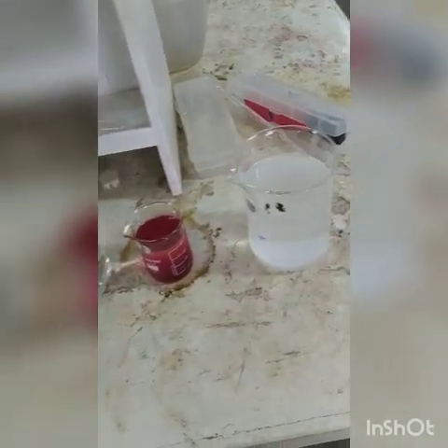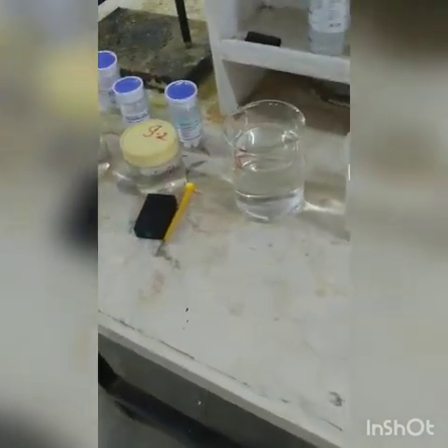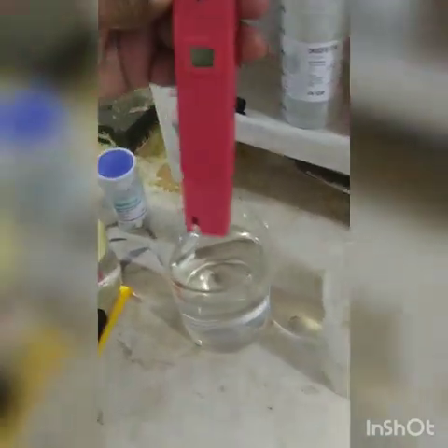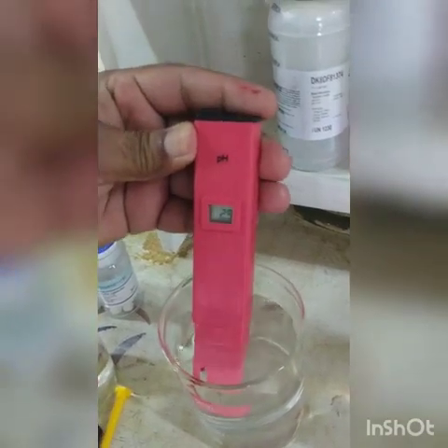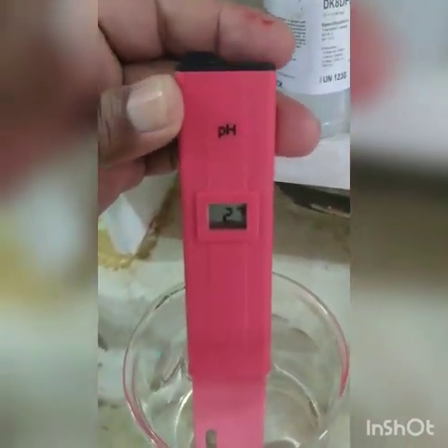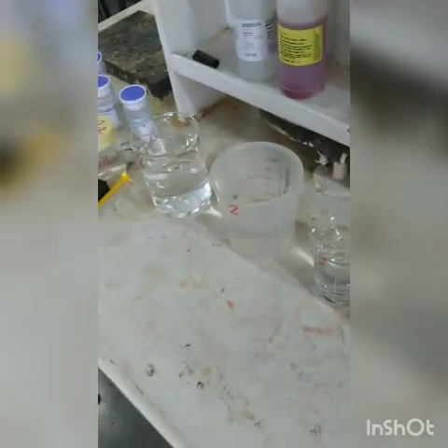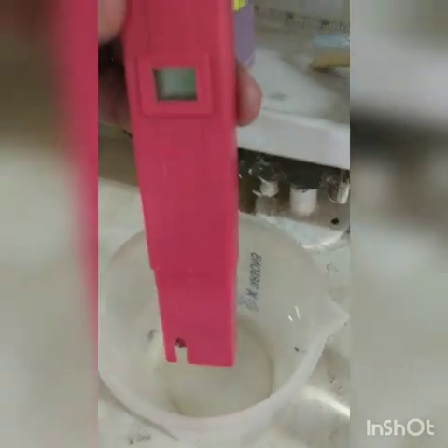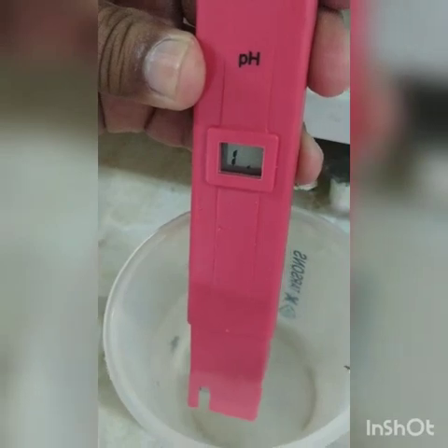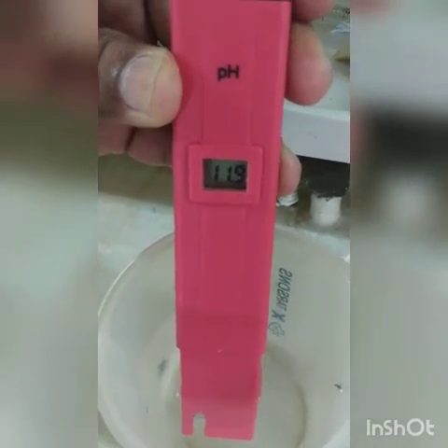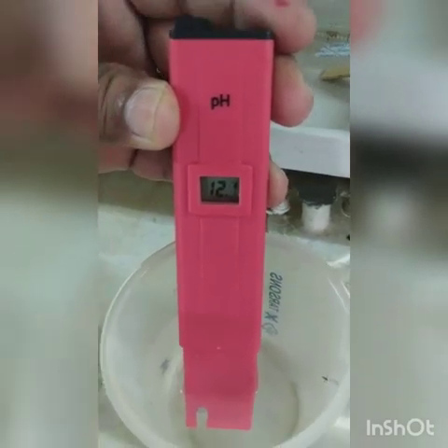So we have 6 different samples that we are going to use for the measurement of pH. So sample 1, you can measure the pH and then we will make the inference. Yes. For sample 1, pH is 2.7. So it is acidic. pH less than 7, the sample is acidic. Again the instrument is washed with distilled water, and we will now measure pH for sample number 2. Now for sample number 2, we are measuring the pH using the pH probe. So it is 12. So this is alkaline.